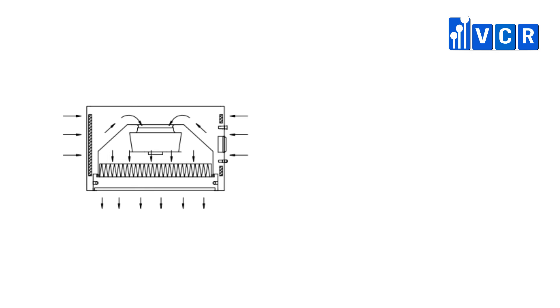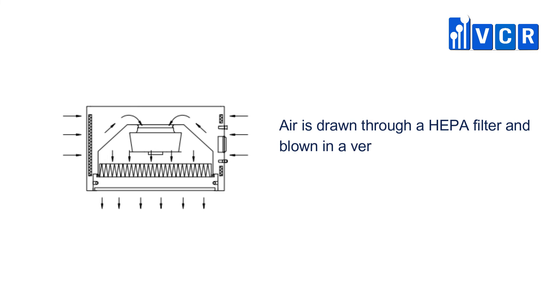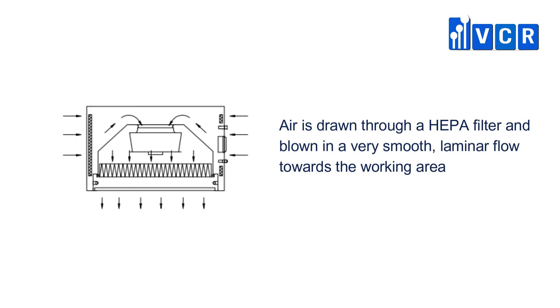Laminar Flow cabinets work by the use of inflow laminar air drawn through one or more HEPA filters, designed to create a particle-free working environment and provide product protection. Air is taken through a filtration system and then exhausted across the work surface as part of the laminar flow process.